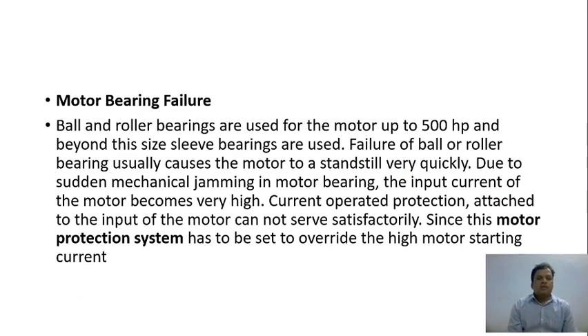So this is the first thing, motor bearing failure. What is motor bearing failure? How does it occur? These are the things to be discussed now, because for the synchronous motor we will be dealing with motor bearing failure. Ball and roller bearings are used for motors up to 500 HP, and beyond this size, sleeve bearings are also used.